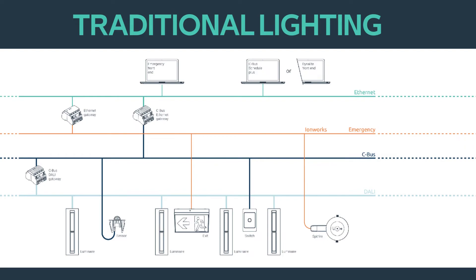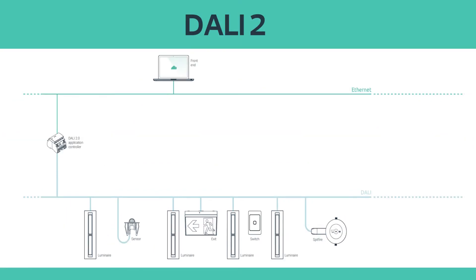With DALI 2, the lighting control wiring has been simplified. Now all sensors and switching devices have been moved onto the DALI line, and DALI emergency light fittings have also been included. This not only saves time, but also saves on cable costs. Installers are now not locked into a single proprietary system — they have the freedom to choose from a large number of certified products for their smarter lighting control project.